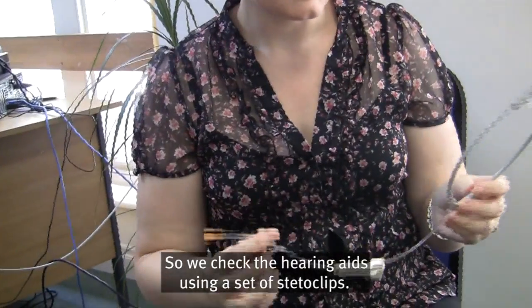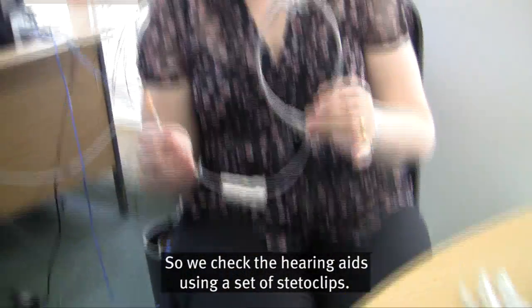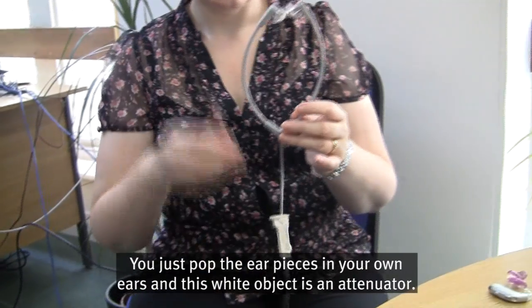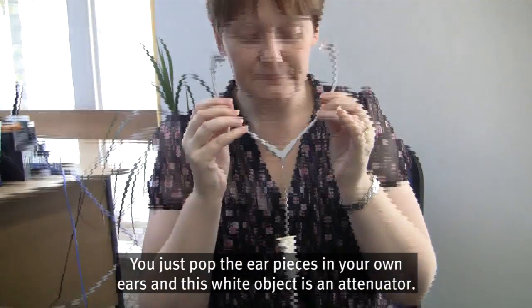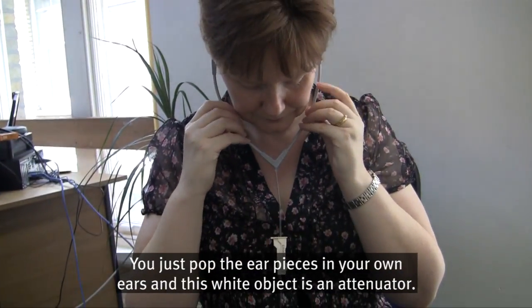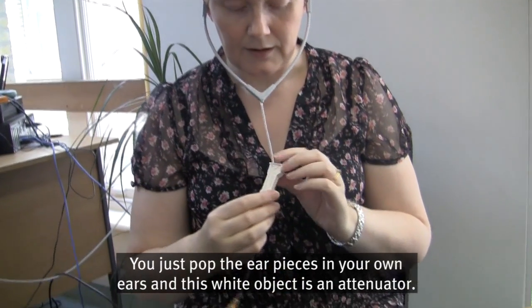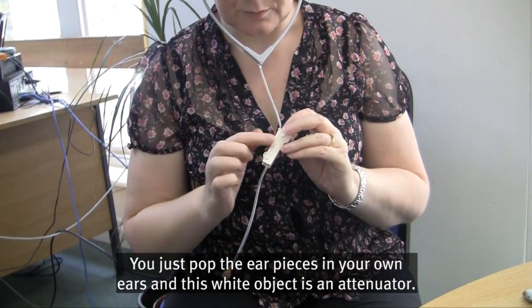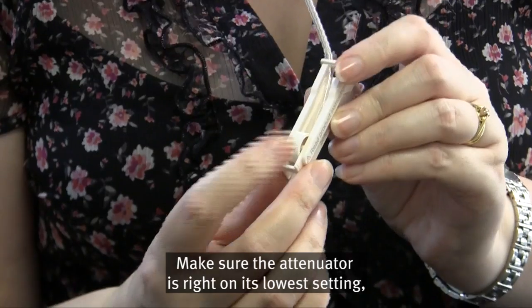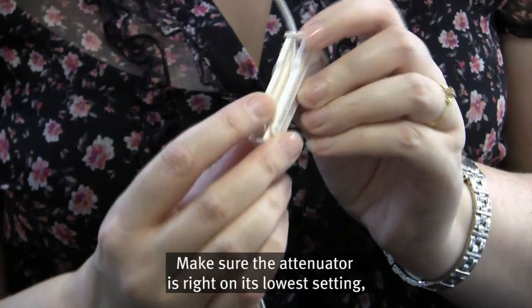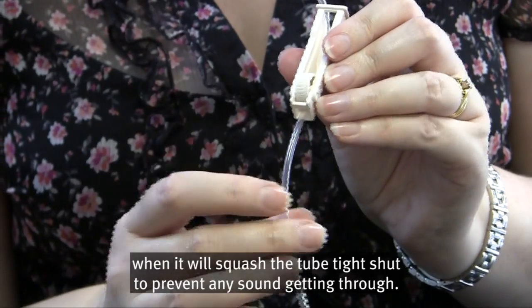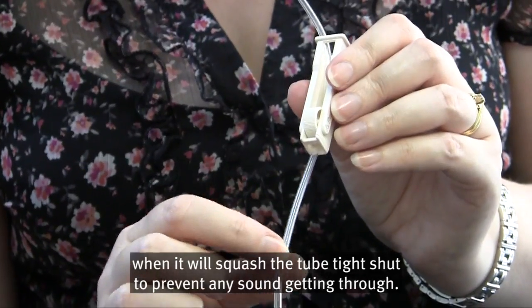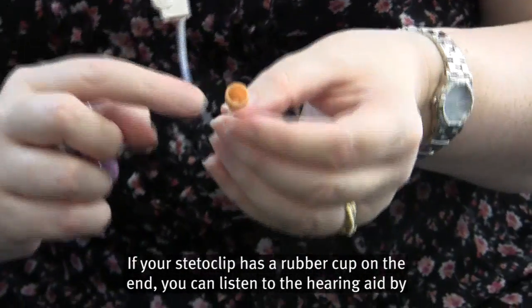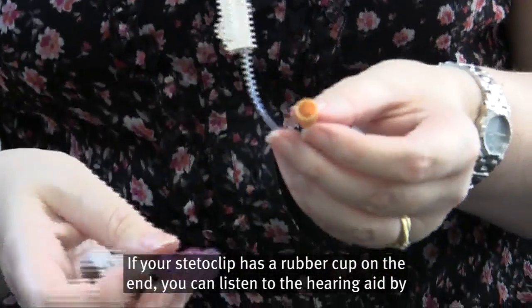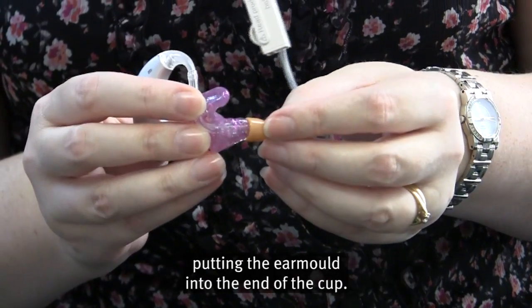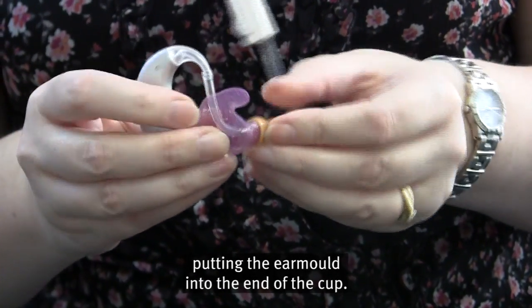Okay, so we check the hearing aid using a set of stetoclips. You just pop the earpieces in your own ears, and this white object is an attenuator. Make sure the attenuator is right on its lowest setting when it will squash the tube tight shut to prevent any sound getting through. If your stetoclip has a rubber cup on the end, you can listen to the hearing aid by putting the ear mould into the end of the cup.